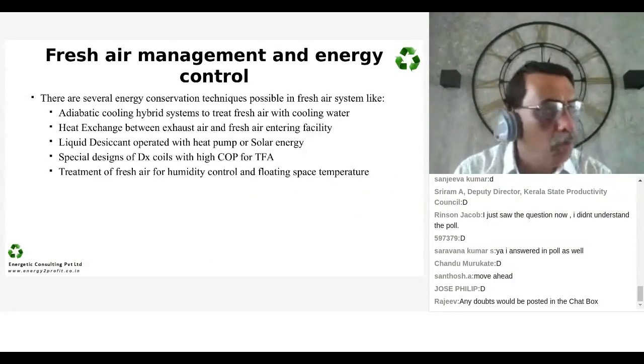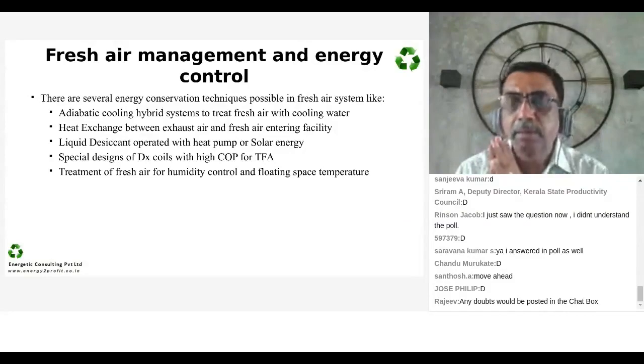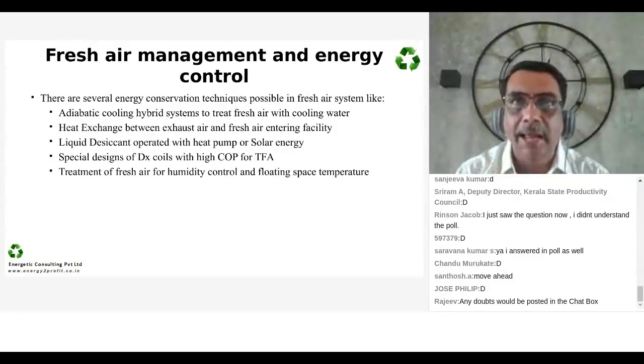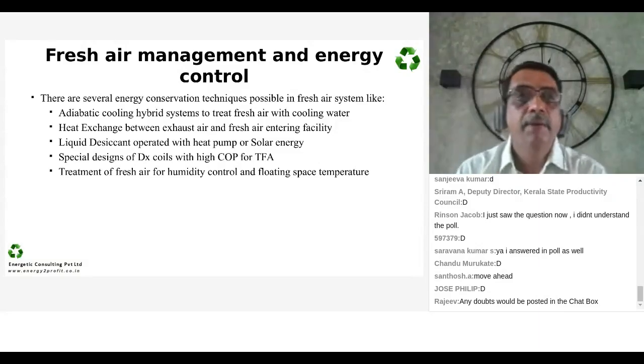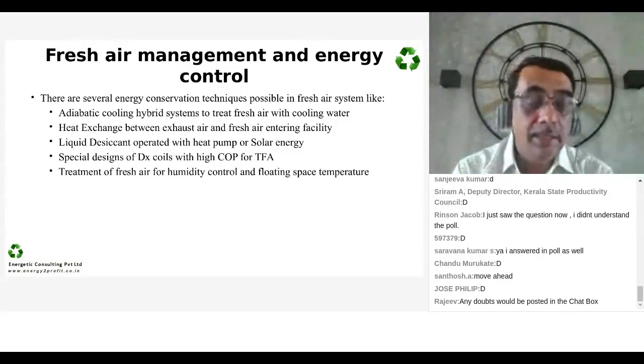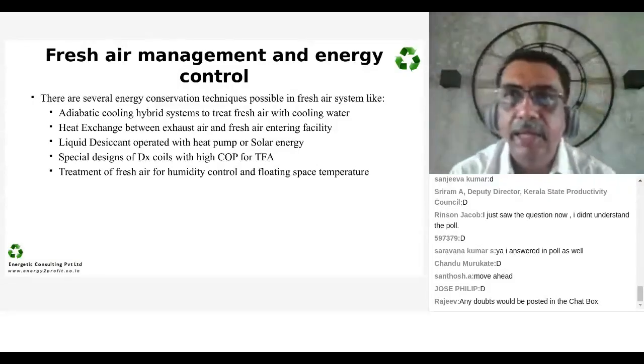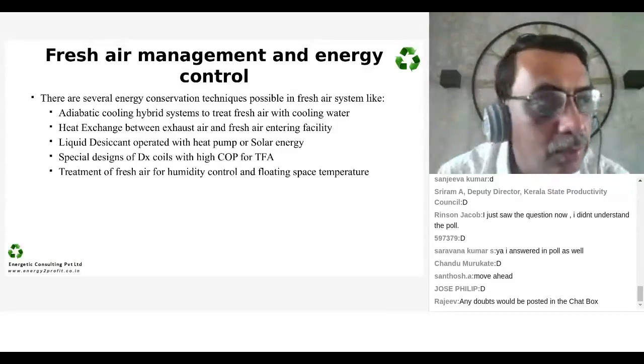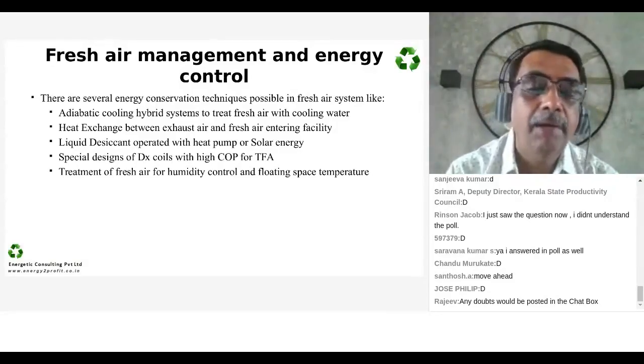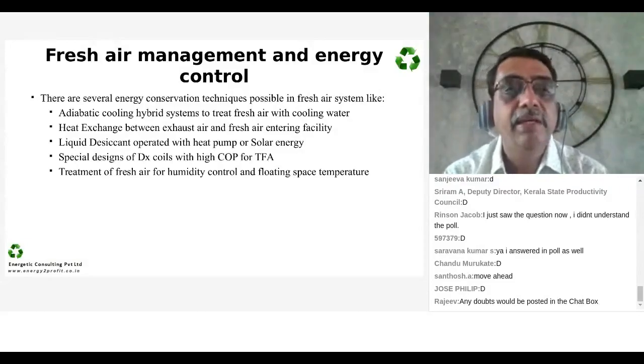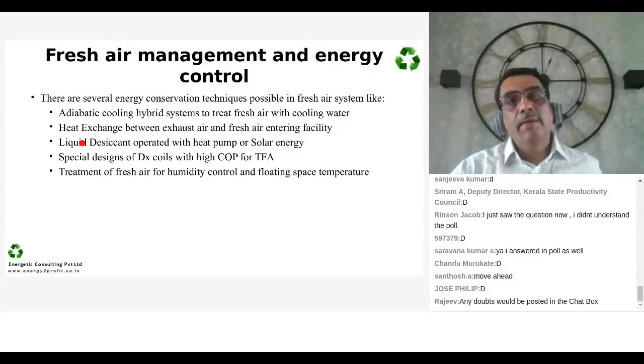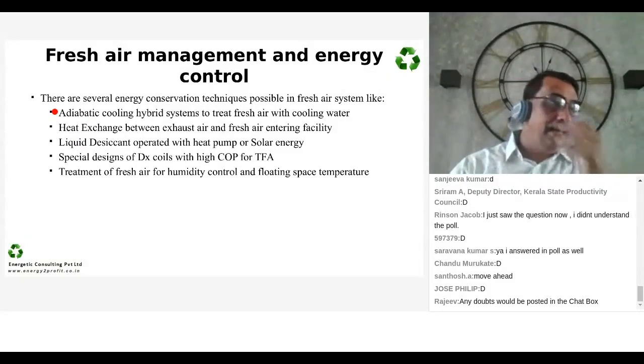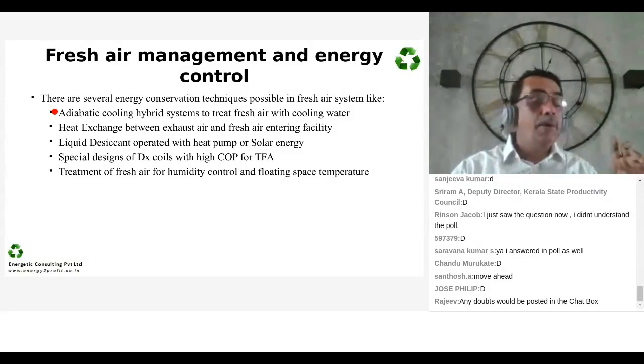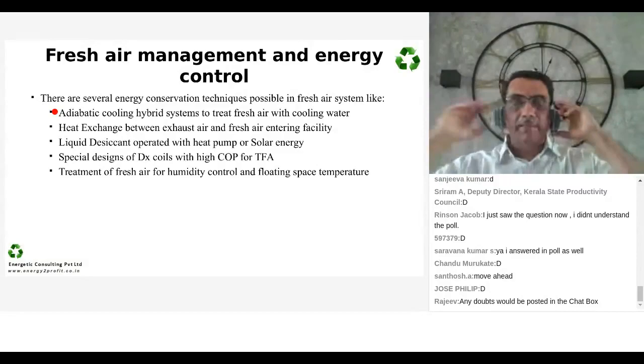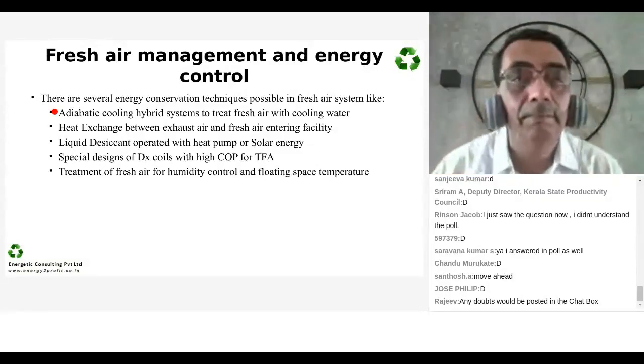Now, first and foremost, most people actually shut off their air dampers for fresh air, feeling that fresh air is an energy guzzler. Fresh air does add to heat load, no doubt, because you're taking atmospheric air into the space, but it is not necessarily the culprit for high energy demand. Moreover, it is required for so many things. You have people inside the area, they need oxygen, so fresh air has to be taken in. You have pressure balancing to be done, and fresh air is required, because otherwise you cannot have pressure adjustments.